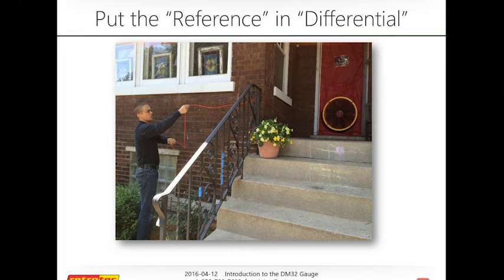The reference tubing is always the starting measurement, and that's important to understand—since it's always a starting point, it's always zero. So this tube's reading is 0, and that's its starting point. Whether the pressure outside is 2,000 pascals or whatever the atmospheric pressure is, it doesn't matter, because according to this tube it's 0. It's about the reference, the difference between inside and outside. So if the pressure outside is, say, 3,000 pascals, and the inside of the house is 3,050 pascals, the reading I get on my gauge is 50 pascals. If that doesn't make sense, I apologize—I'll explain further.